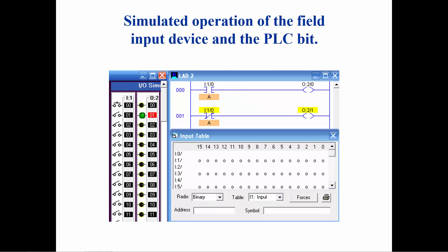This is an example of both an examine if closed and an examine if open instruction. Both instructions reference the same input address, I colon 1 slash 0. When the switch is open, the examine if closed on rung 0 will be false and there will be no logic continuity to the output energized instruction, and therefore output O colon 2 slash 0 will be off. At the same time, the examine if open instruction on rung 1 will be true, allowing logic continuity to the output energized, therefore turning on output O colon 2 slash 1.